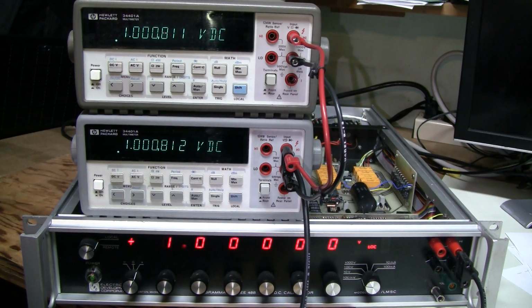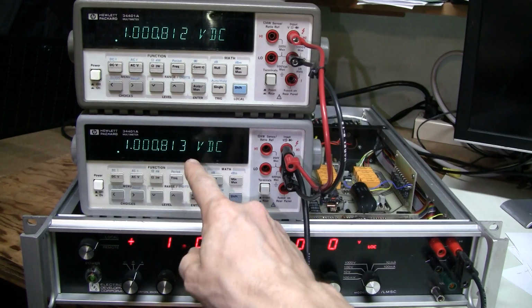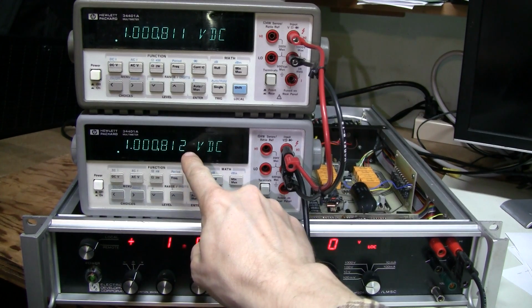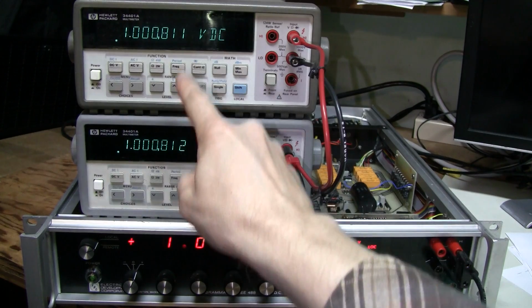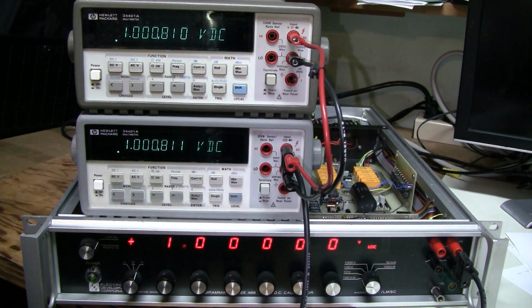Check this out. I've got another Hewlett-Packard 34401A meter, and I warmed up the equipment for several hours and switched the meters into a slow mode, so it takes them several seconds to settle, but makes the comparison easy. So the last digit is 1 millionth or 1 ppm, and as you can see the meters disagree by about 1 ppm in this range. But the calibrator is out by about 810 ppm, which is way too much. It definitely needs an adjustment.